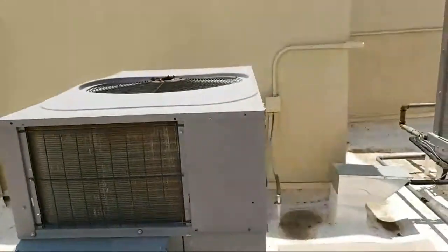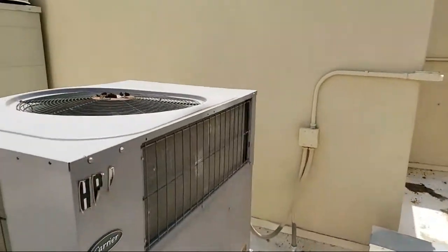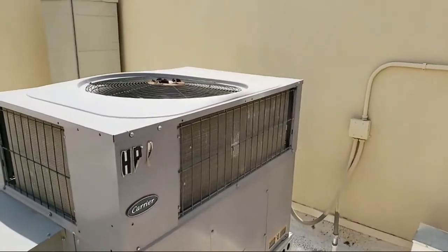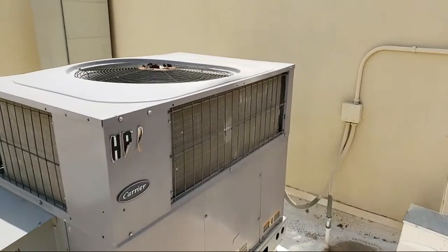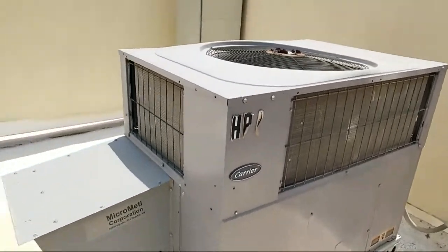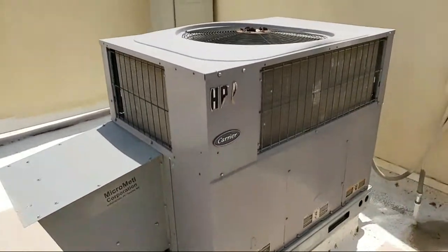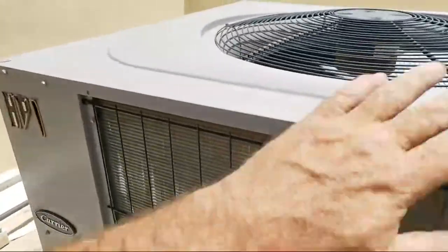Now it's not. And I added those sensors there last year because somebody had them overridden. And then if they cleared the override, it would shut down and stay in economizer. Well, this time I found them in override set for 0 degrees instead of reading at 103 degrees when I reactivated them. Every one of these was set that way. So they have voodoo. I shouldn't say voodoo, but they got gremlins in the controls.